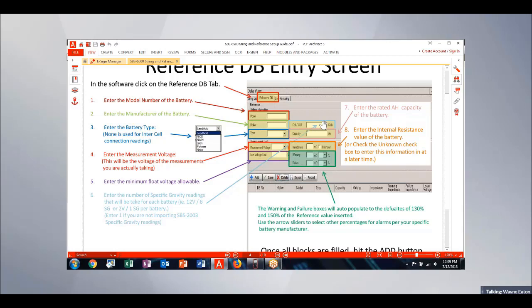On the right-hand side, we have a cells per jar block. So this block is always going to be 1, with the exception of if I'm using the SBS-2003 digital hydrometer to import specific gravity readings from the cells as well. And I have like a 6-volt battery and I'm measuring 6 volts and I'm measuring the internal resistance of that 6-volt block. But then I'm going to go back and I'm going to take 3 specific gravity readings for the 3 cells that are within that block. Then I could put a 3 in this space and it would leave me 2 space holders for those additional specific gravity readings.